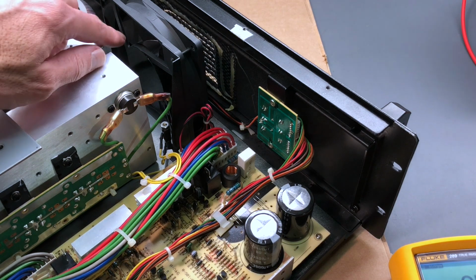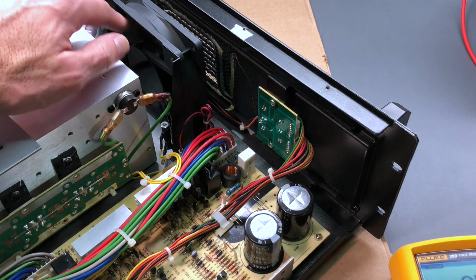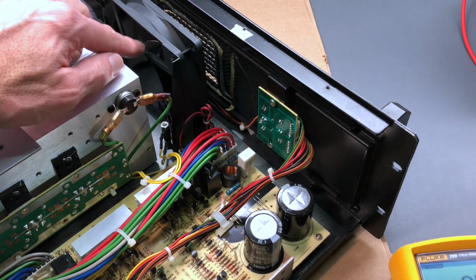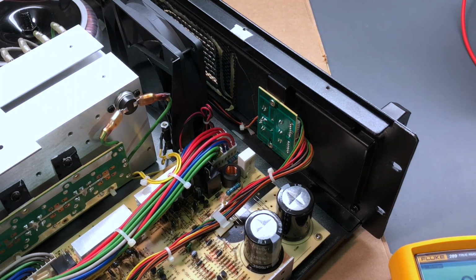A motor like this with electronics will get to a point where it just stalls. It can't run anymore because the electronics won't operate correctly, but when it does that, it still draws current, and that current varies. It doesn't work the same way as current draw on a brush type motor, so some different issues start to happen.